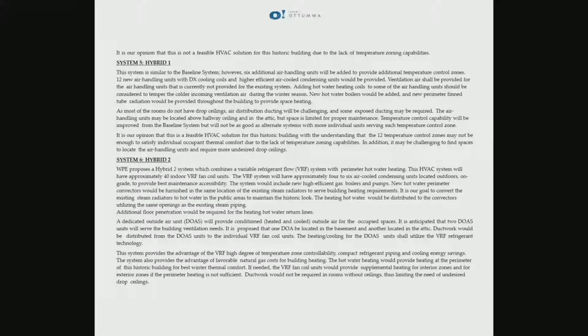That's what we came up with for our systems for evaluation. We recommend systems 5 and 6. We think the other options were just thrown out there but don't really meet good comfort control and temperature controllability in this historic building, because they don't utilize the perimeter hot water system and natural gas usage, which we understand is favorable for buildings like this.